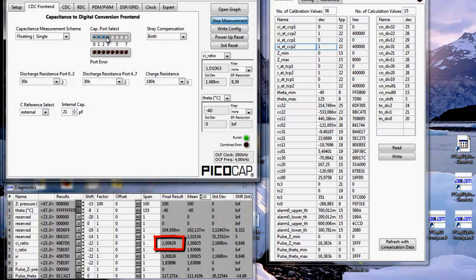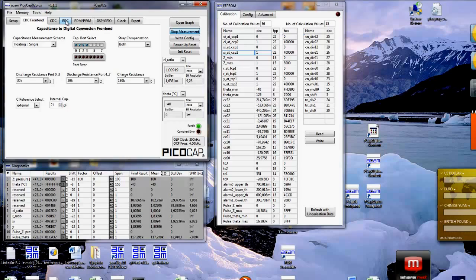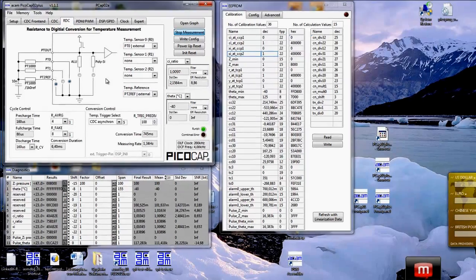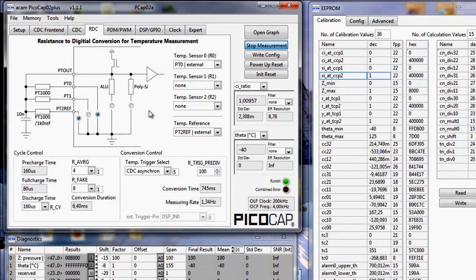Also the ports are enabled correctly from 0 to 3, and I have a floating single set with a stray compensation on. So that way I have the configuration adapted to my needs from a sensor setting side, and I will now do the same for the temperature sensor. For this I change to the RDC tab, and you see here the settings available for the temperature sensor. You can either connect a temperature sensor like a PT1000 externally, or you can use the internal aluminium temperature sensor, and the same is true for the reference. That can be an external resistor which should be in the same range as the temperature sensor, or you can select the internal polysilicon reference.